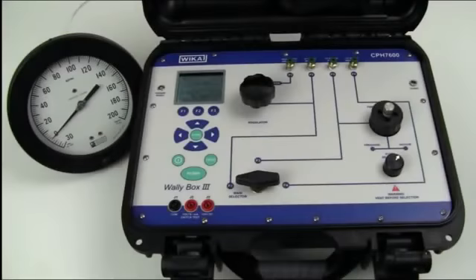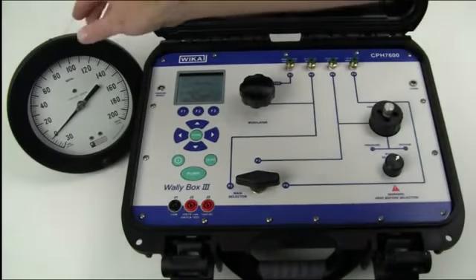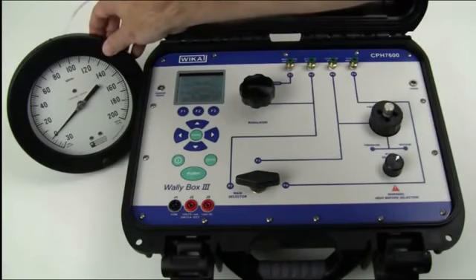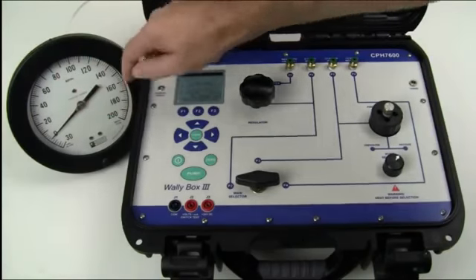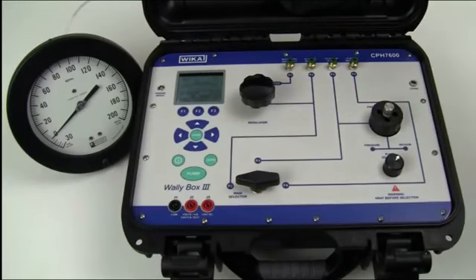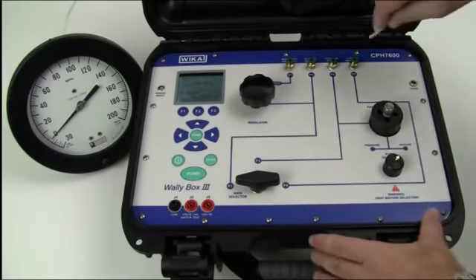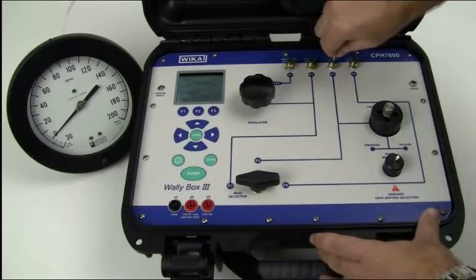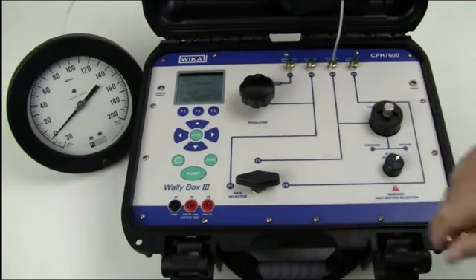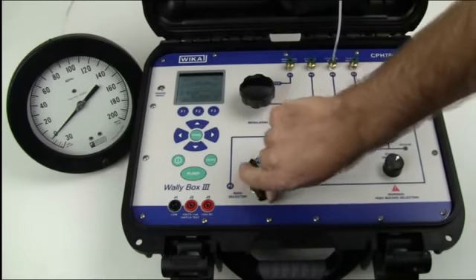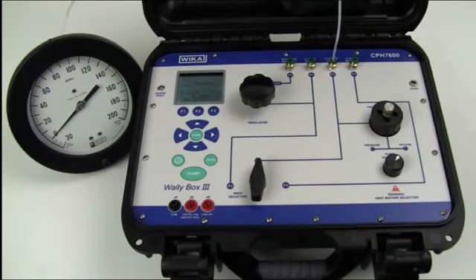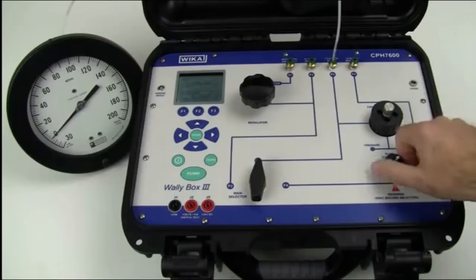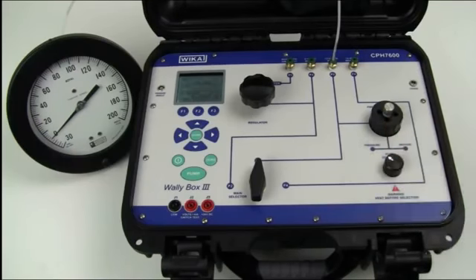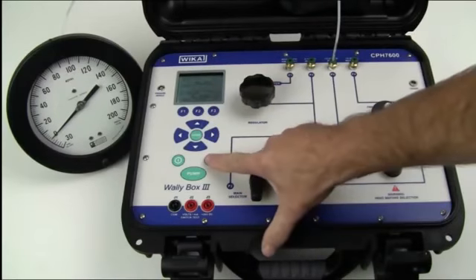In this demonstration we're actually going to calibrate a device under test, which is an analog gauge, which is a vacuum to 200 psi. So in this case, with one of the pneumatic pipes as supplied, you will need to connect it to position P3, put your selector switch onto position P3, choose whether you want to do a vacuum or a positive pressure first, then check your sensor and perform a 0.